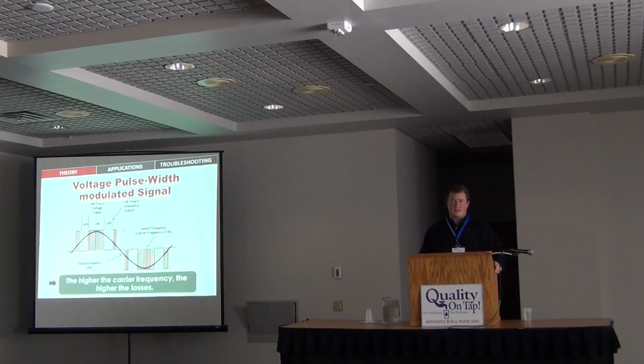If it's a clean scenario, as long as you're aware that you need to make sure your fans are still working, and that the input side through the ventilation and within the enclosure is clean, periodically you want to look at it for sure. But how often depends on the application where it's installed. My house gets dirty when I don't clean it in a month, but it really depends on your plant. Some plants are immaculately clean, with a guy there all the time cleaning. Other plants are a little smaller, with less staff, and maybe they don't have the time or effort. In some dirtier electrical rooms, you want to look at it more often. But hiring someone outside to clean it, you could probably shut the upstream breaker off and do it yourself too.